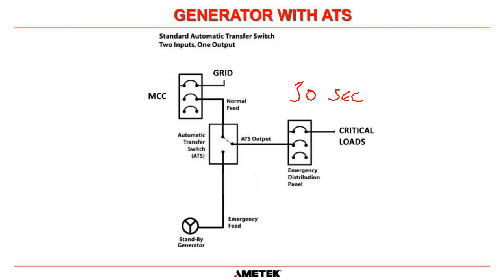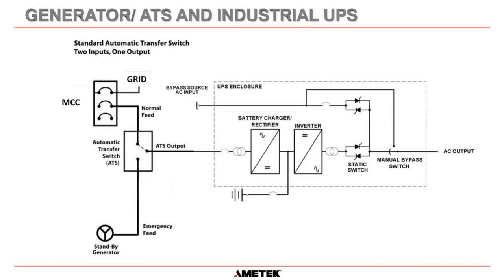controls, that's not acceptable. So the next page is a very common arrangement that we will see. And all they've done is they've put one of our AMETEK SCI UPSs on the output of the automatic transfer switch. Okay, and then our critical loads are on the output here. So in normal operation, the grid goes through the MCC and feeds the input to our rectifier. Okay, that maintains the charge on the batteries and also supplies power to the inverter to convert the DC back into AC, and then that goes out to our AC distribution panel.